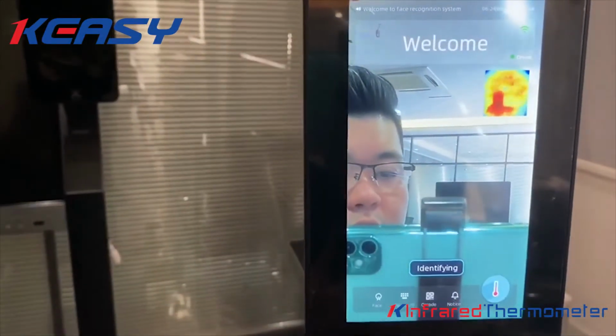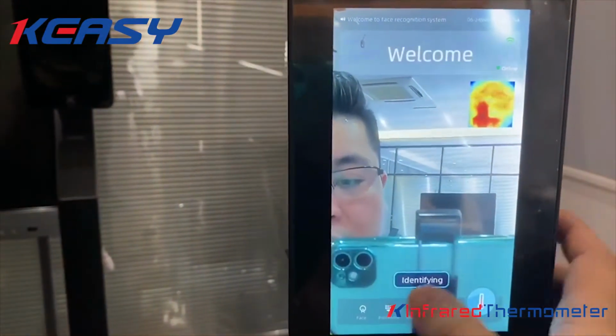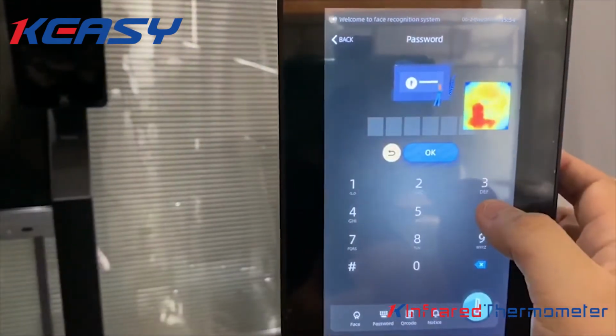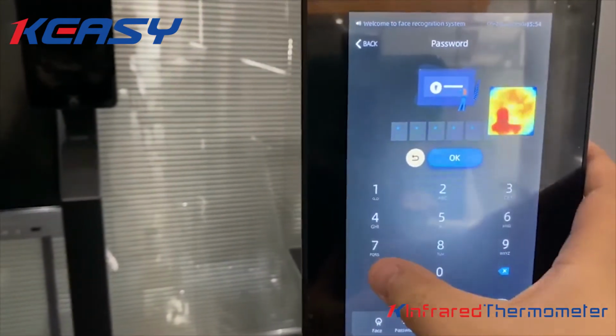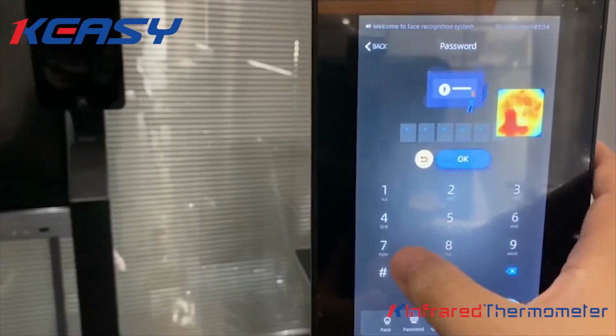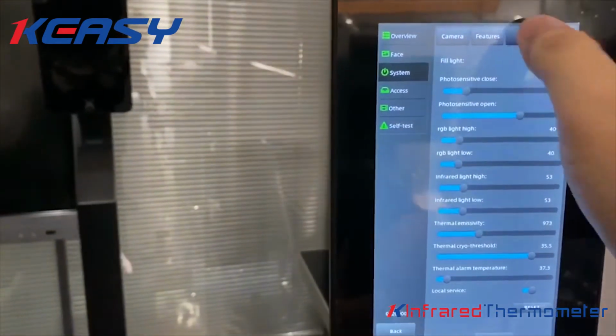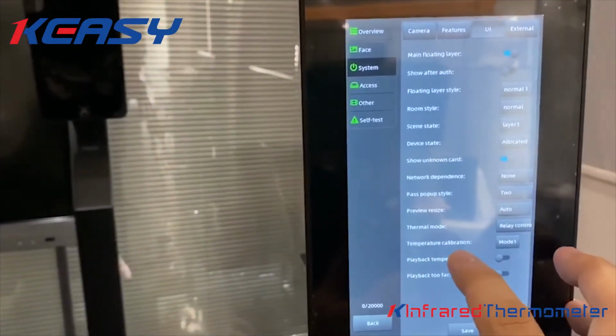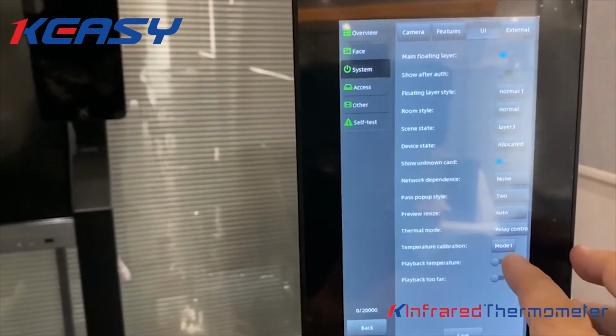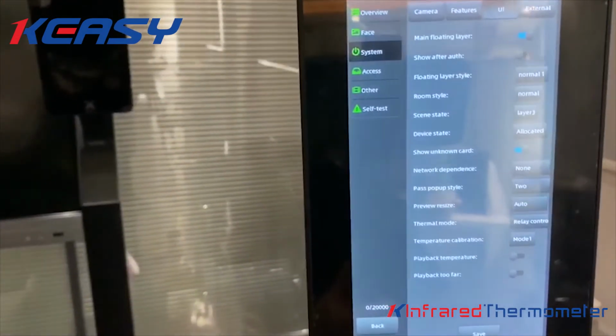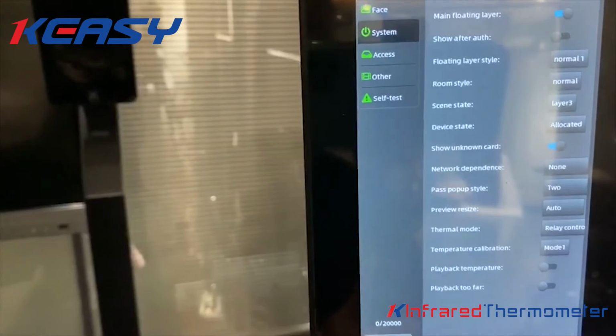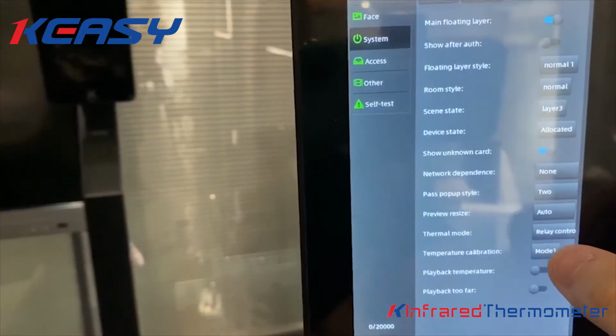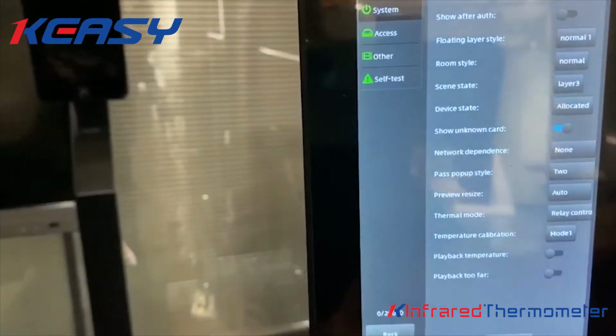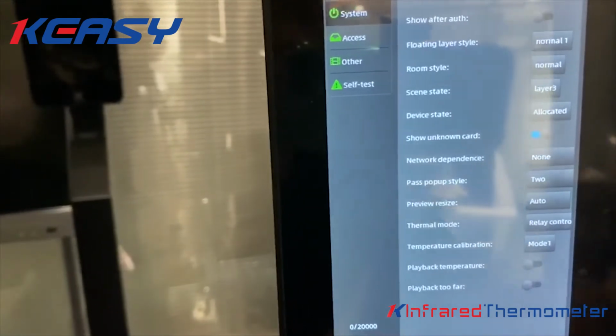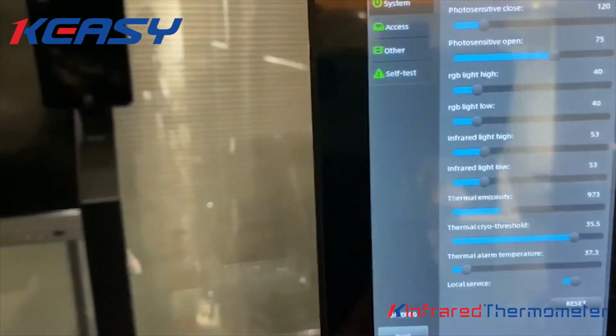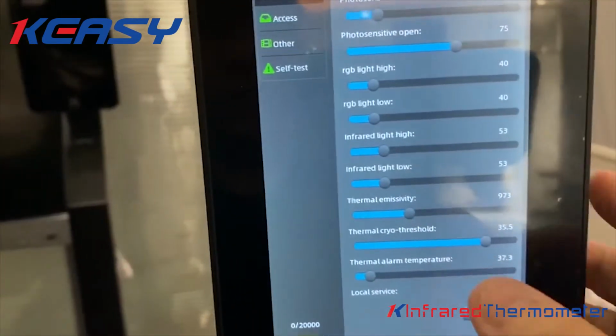Okay, after the device powers on again, we can go to the platform to start the temperature calibration. Please make sure the temperature calibration mode is in mode 1. After we finish the calibration, we have to set it back to mode 3, because mode 1 is the engineer mode. And now we have to go to external.